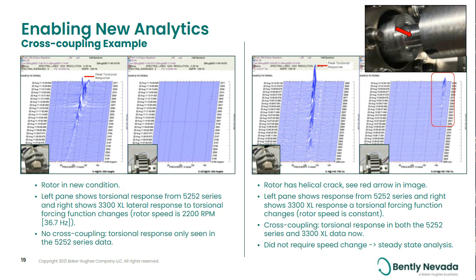The right side of the slide shows data taken from the same probe, but later in time after a crack has developed on the shaft. The inset in the top right shows this crack. It visually appears as a hairline fracture, and it can be difficult to see in this slide. The left pane again shows the torsional response as the torsional perturbation frequency is increased. The 5252 series probes show the expected torsional response and increase in amplitude as the excitation frequency coincides with the resonant frequency.